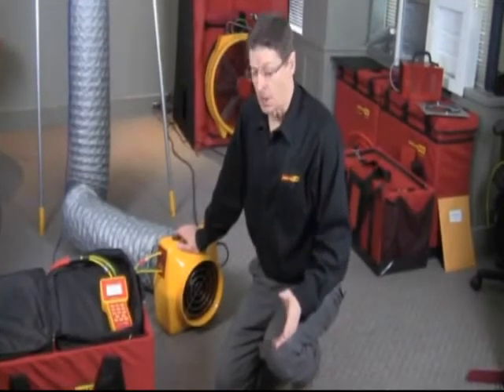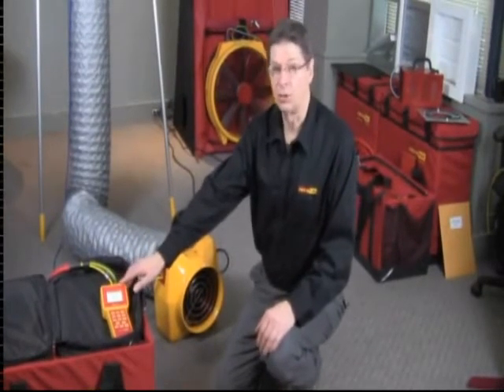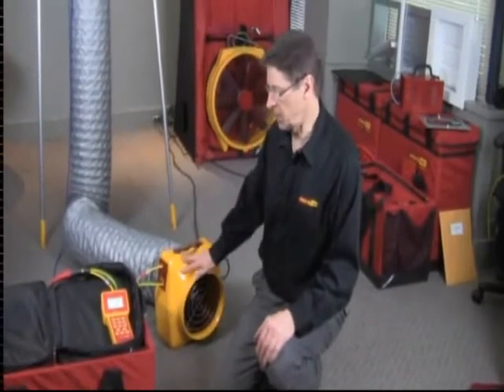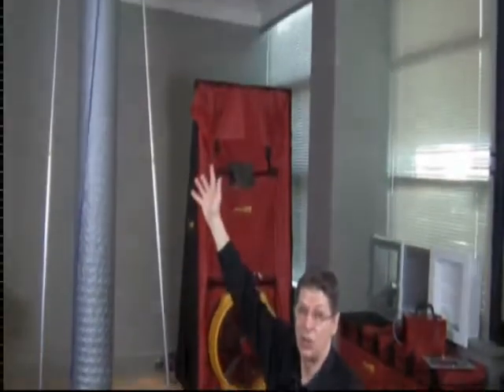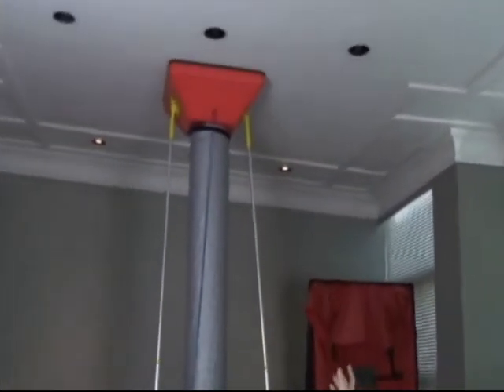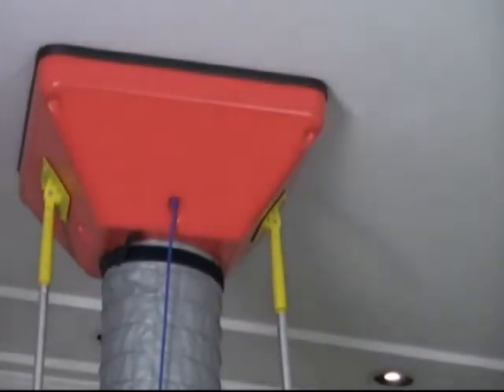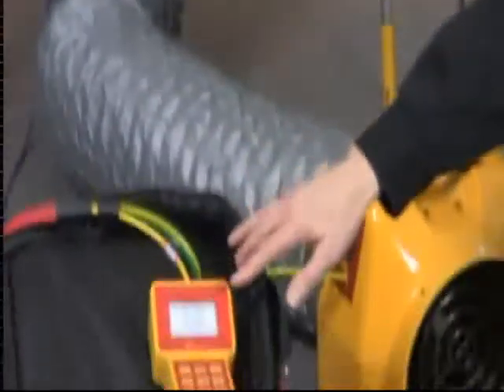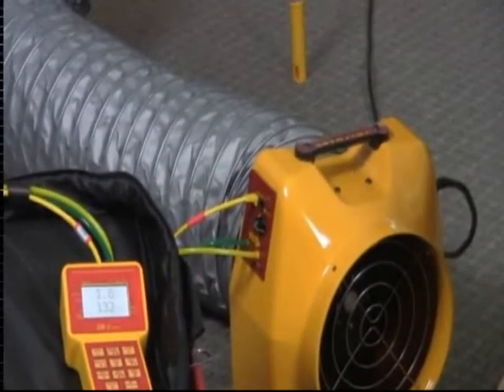Here we have our duct tester running as a powered flow hood. On the gauge, we've set it to zero — we'll show you how to do that in a minute — but it's actually running right now and measuring the flow out of this supply register in real time. We've got the flex duct attached to our large pressure pan, coming down to the inlet of the duct tester, and we're measuring the flow here at around 130 CFM.